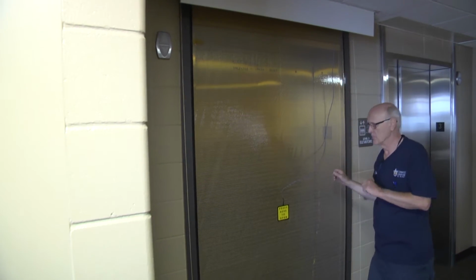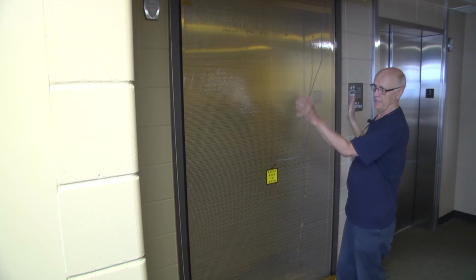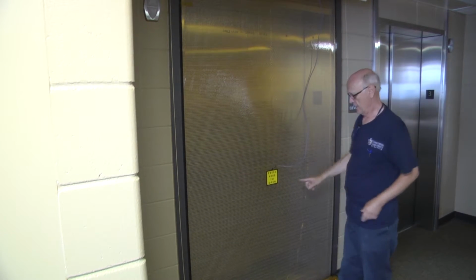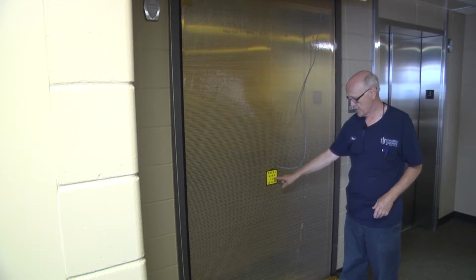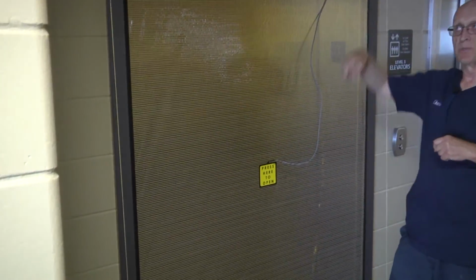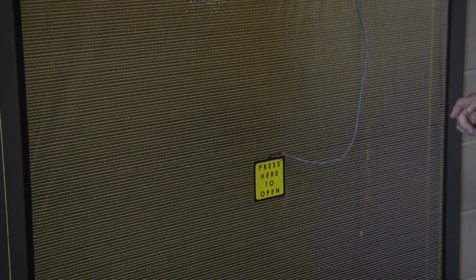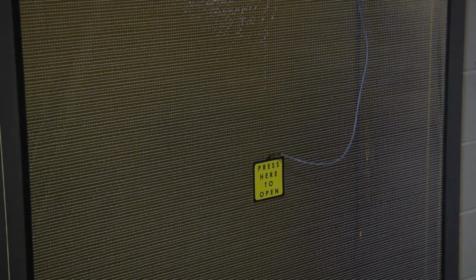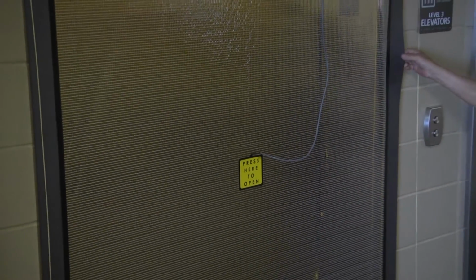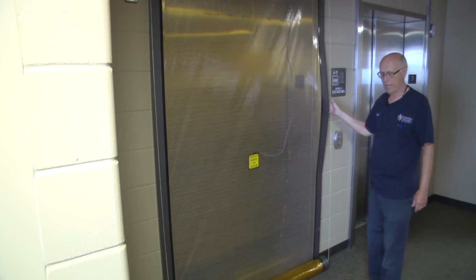Where the problem comes in is if someone is in the elevator and opens up on this floor, they see this screen and they kind of panic. If they press on the inside, you'll see it says press here to open. If they keep pressing it, the power system will send it back up, but it's only temporary if it's still in the fire alarm mode. If they do have to get out and it's an emergency, this is just a magnet, so if they push away from here, they will be able to get out.